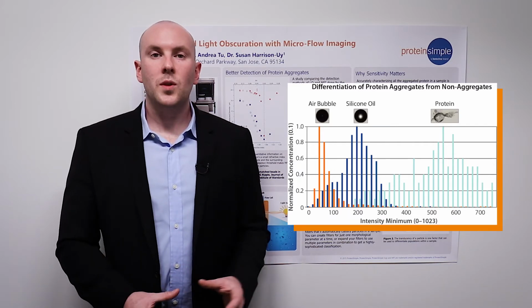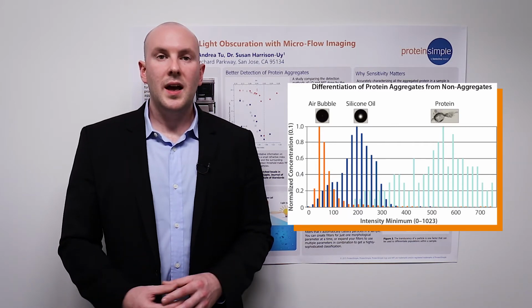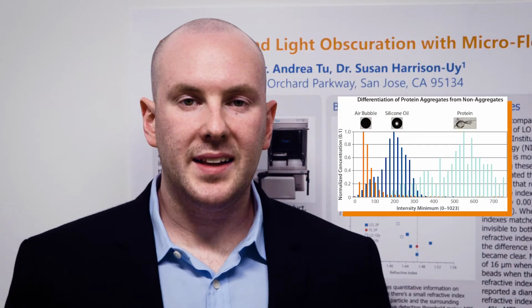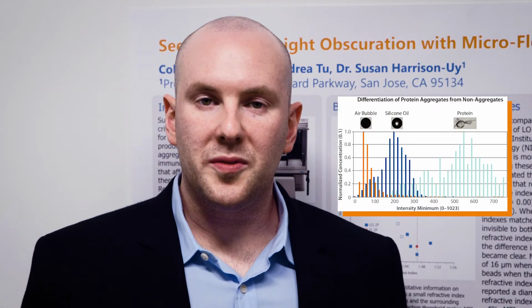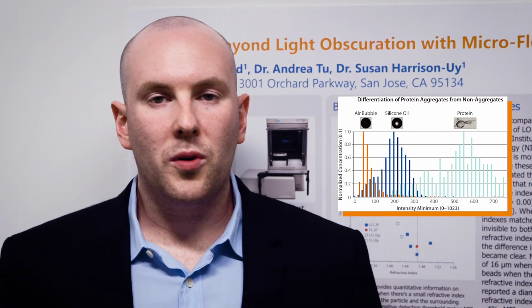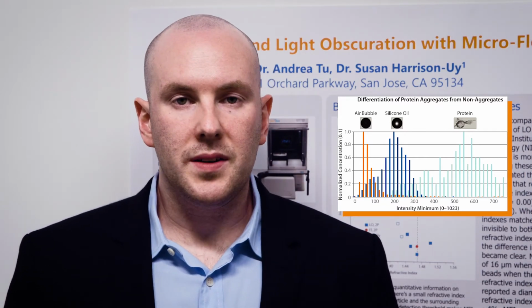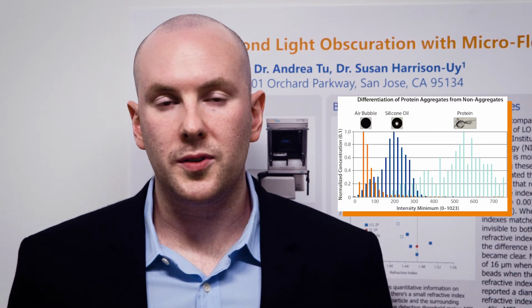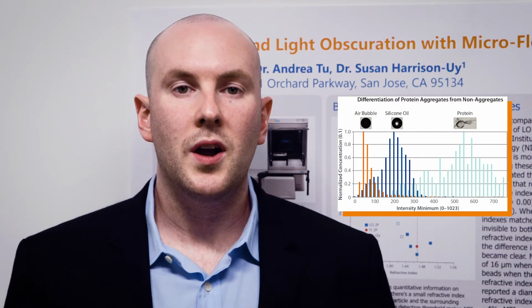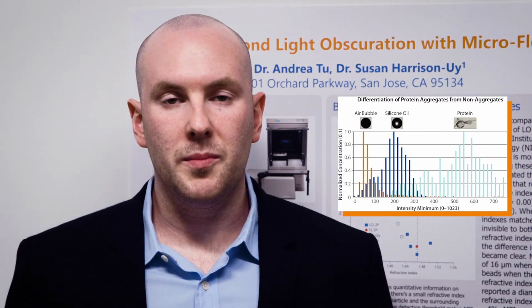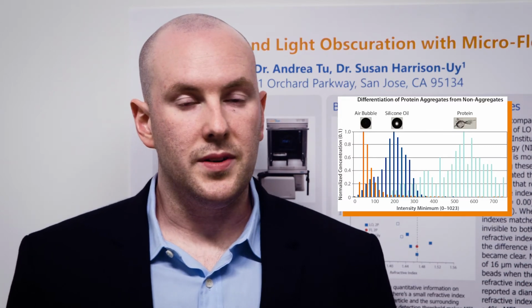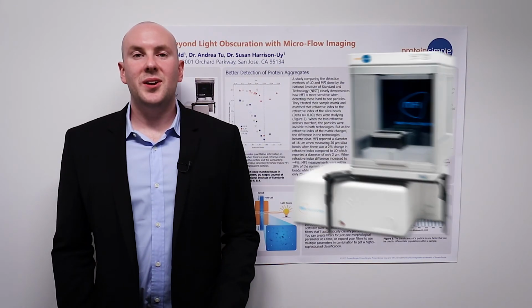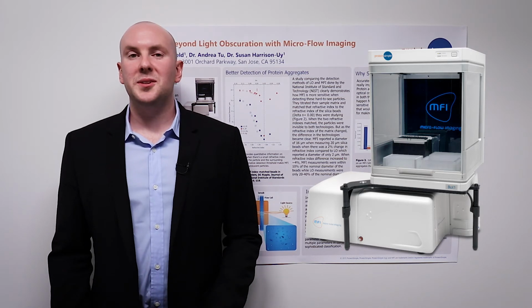Now, the silicone oil drop, with its dark outline and its bright center, has a slightly lower score. And then the highly opaque air bubble scores very low for intensity minimum. So this is one morphological parameter that can be leveraged to differentiate these three different particle populations. Now, people commonly employ multiple morphological parameters in conjunction with one another to form filters which can be highly discriminatory in terms of their ability to differentiate particles.